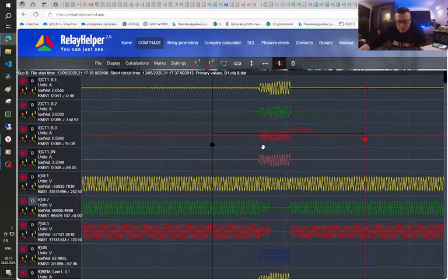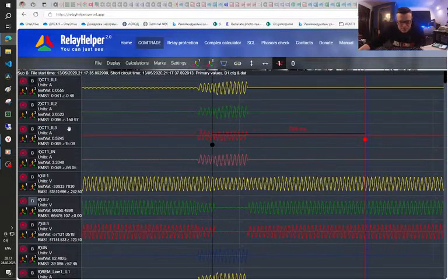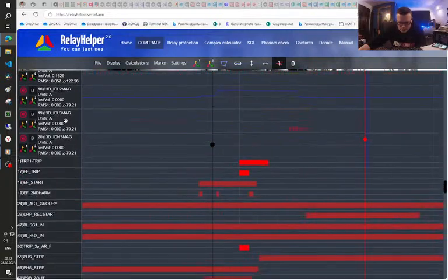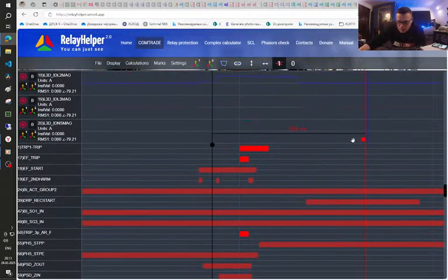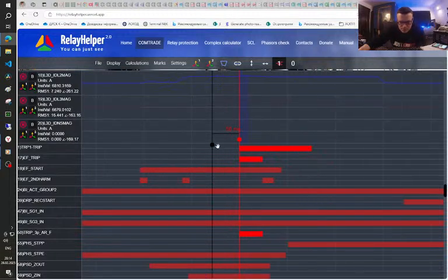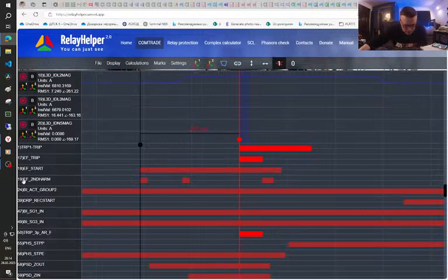So what was more interesting in this particular case? Here we have a trip, 20 milliseconds, but look at this digital channel that's called EF second harmonic.